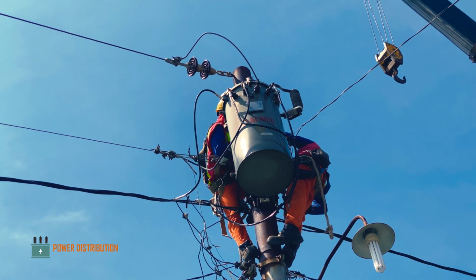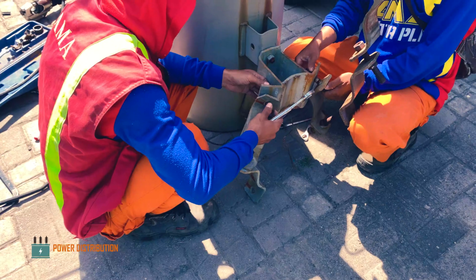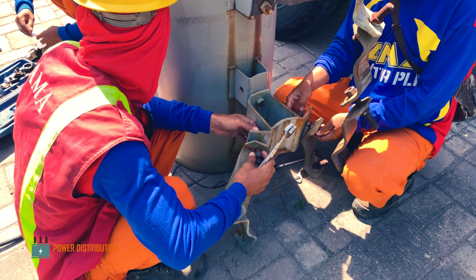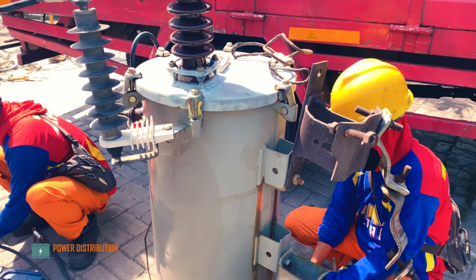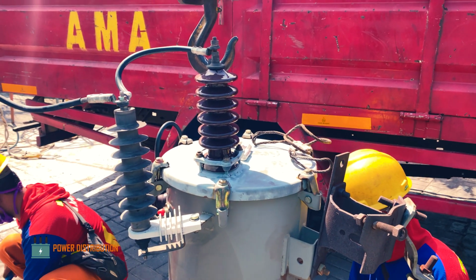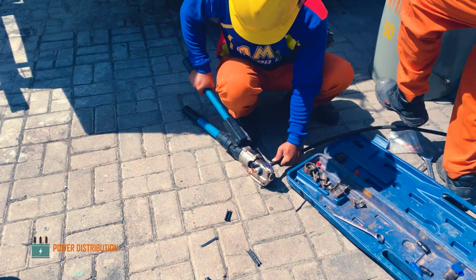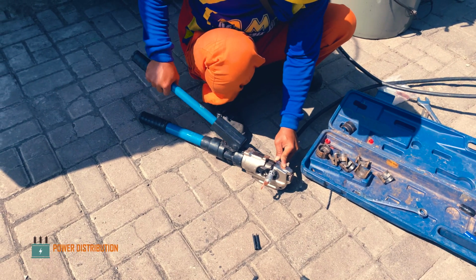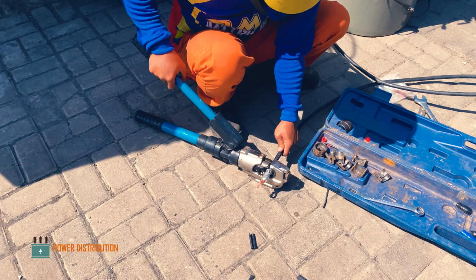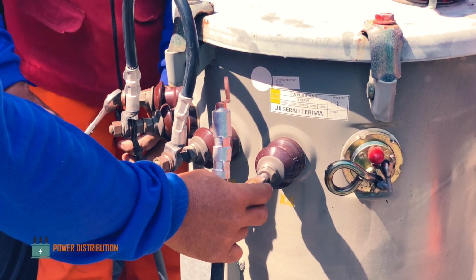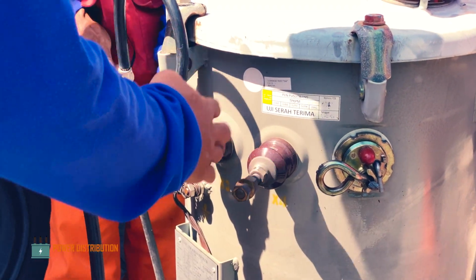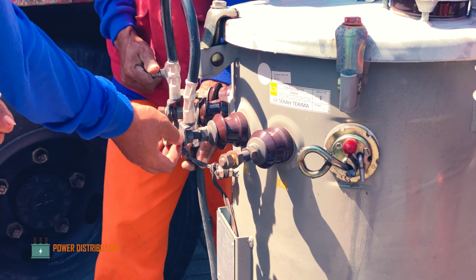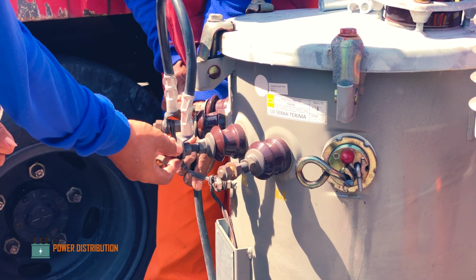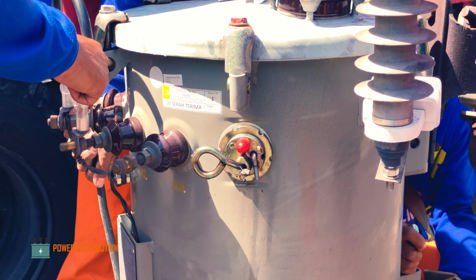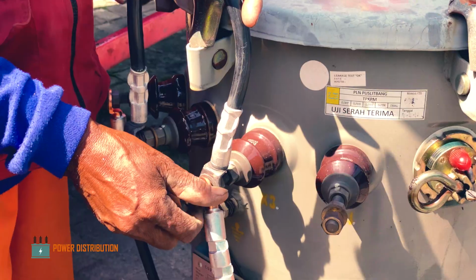After being de-energized, the lineman ascends to the pole and the ground crew prepares the transformer by installing the brackets and then prepares all the jumpers necessary for making the connection between the new transformer and the existing line. This transformer will operate in normal distribution mode, indicated by a common jumper in the middle of the secondary bushings.